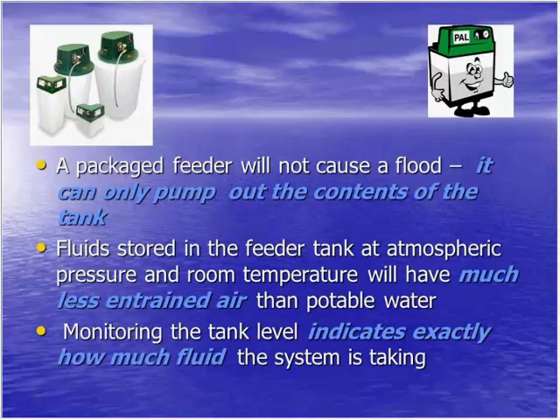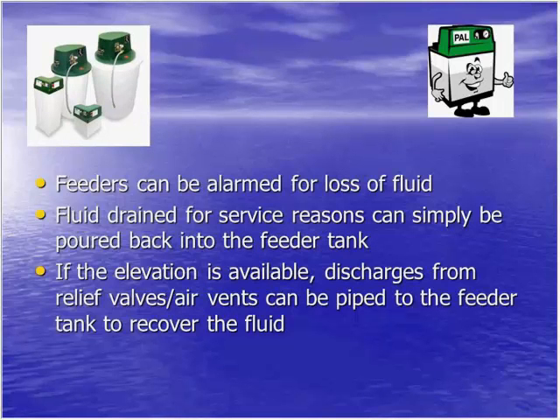Feeders can also be alarmed for loss of fluid or pressure. So in the event you're at a residence that is uninhabited for a good portion of the year, a vacation home, low fluid level or pressure loss can actually be a good indication that there's a leak or something wrong with the system. So essentially it's a set of dry contacts on the units or on the optional low level alarm panel that can be tied into whether it be a building management system, home security system, or an interlock to turn the boilers down, whatever you want it to do. It can be a means of an indication of a leak or that something's wrong with your system.